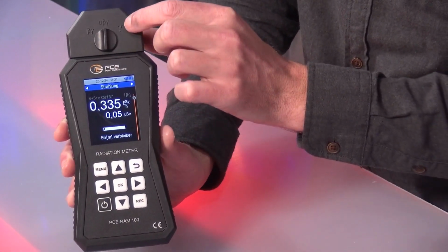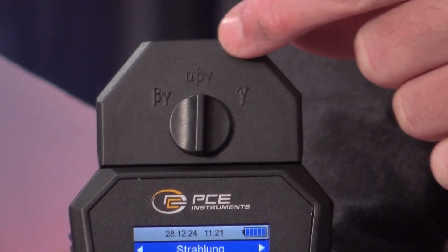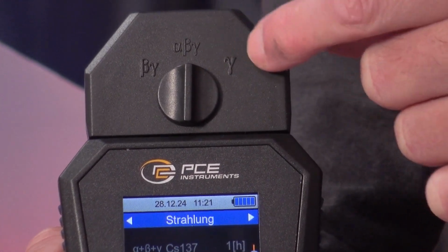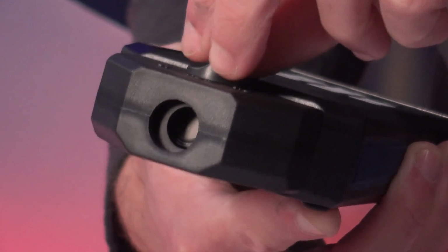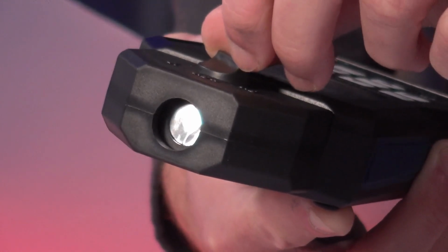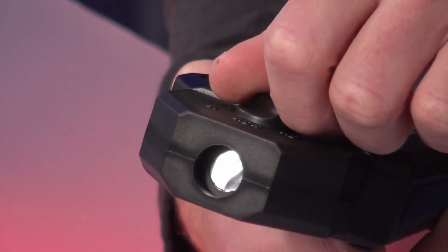And if we look closely at it with the camera, we can see some letters. Here on one side, it measures beta and gamma radiation. Then I can switch it over here for beta, gamma, and alpha radiation, and over here for gamma radiation only. Now, how does that work? When we look at it here with the camera, we see different materials that shield the beam path accordingly. These shield the alpha radiation, or the alpha and beta radiation, which are easier to shield than the gamma radiation. And thus, it gives us the opportunity to find out more precisely what type of radiation we are dealing with. In other words, we are able to classify the radiation.